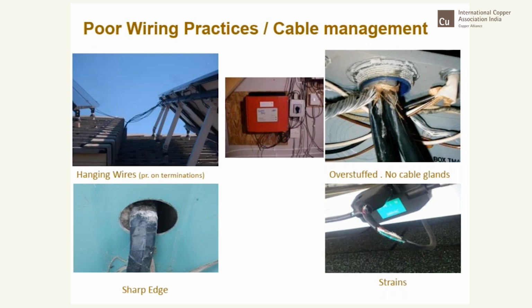And then we are overstuffing. You are putting so many cables into a small orifice, and it gets stressed, and then maybe it gets cut also. And then there is no cable gland, which means stress can directly come on the cable and the cable insulation, and then you are going to create strains, as you are seeing in the bottom one.